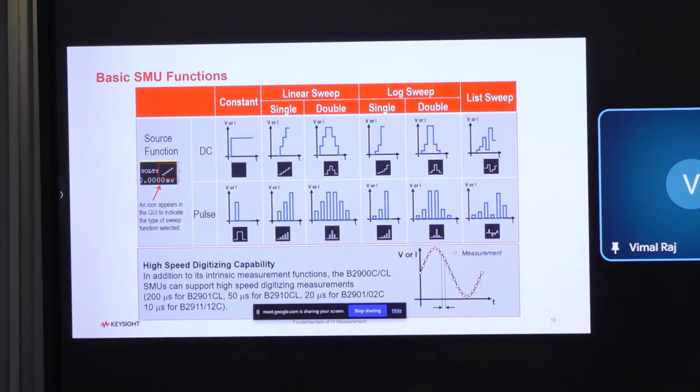When you put it in the linear double, you can see what capacitance effect will be there in the sample. Maybe transistors or IGBT MOSFET will have some capacitance effect. That also we can see in the linear double or logarithmic double, because when you are sweeping the voltage, sometimes the small material will get charged. In the linear double, when you are sweeping down, we can get the hysteresis value that you can achieve using our SMU. And the same pattern we can use for the logarithmic sweep.